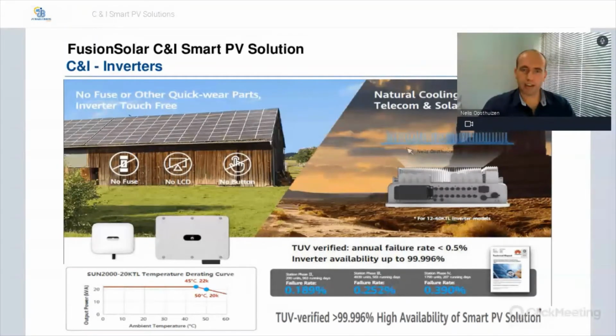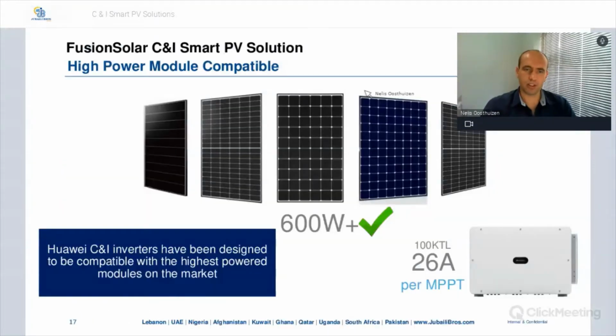So also adding to the reliability of the Huawei inverters. Huawei, as we all know, is actually a telecommunications company, and they've used all of the experience from the telecommunications and combined it into the solar inverter department. So they make use of natural cooling, and this natural cooling method has been verified by the telecoms and solar applications. So all of this combined, the natural cooling, no fuses, no LCD, and no buttons, all allows for the inverters to have high reliability. So you've got lower failure rates, and then obviously lower failure rates equal higher yields, which then increases your system performance.